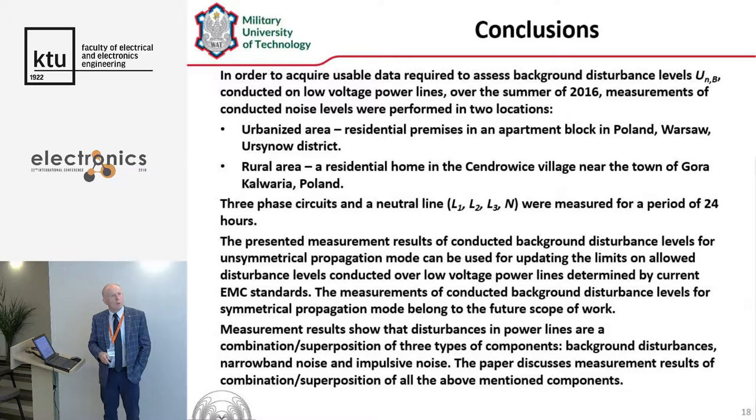Conclusions. In order to acquire usable data required to assess background disturbance levels conducted on low voltage power lines, over the summer of 2016, measurements of conducted noise levels were performed in two locations. In urban area in Poland, Warsaw, and in rural area, a small city, Kalwaria, near Warsaw. We have measured disturbance on three power lines and neutral lines. The presented measurement results of conducted background disturbance levels for unsymmetrical propagation mode can be used for updating the limits of disturbance levels conducted over low voltage power lines determined by current EMC standards. The measurements of conducted background disturbance levels for symmetrical propagation mode belong to the future scope of our work.